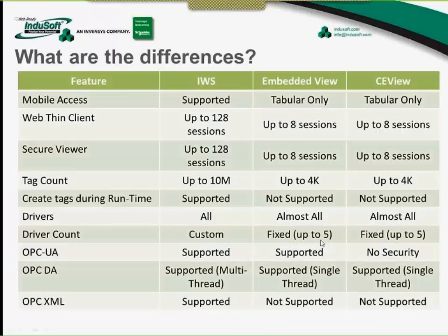Okay. So that being said, another limitation that we have is OPC UA. OPC UA is actually supported across all the different platforms, but if you're using CE View, then there's no security. We don't have built-in security for OPC UA when you are using CE View. It also makes some sense, because if you're using CE View, in the majority of cases where we saw this, your hardware is usually not powerful enough to handle the encryption required there. So that's one of the reasons why we didn't make the effort to make that available. But let us know if you need this, because we might put it in our roadmap in the future.